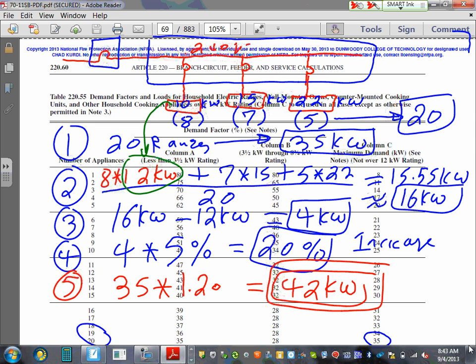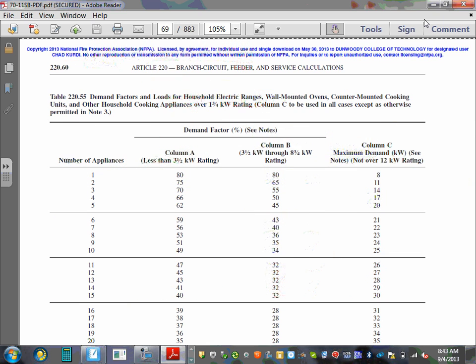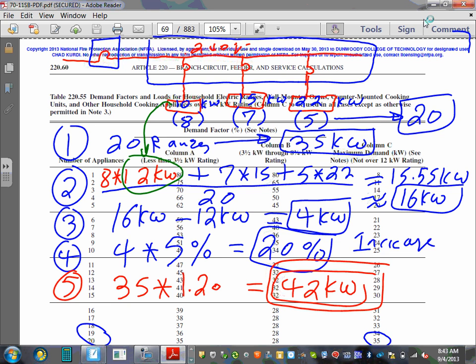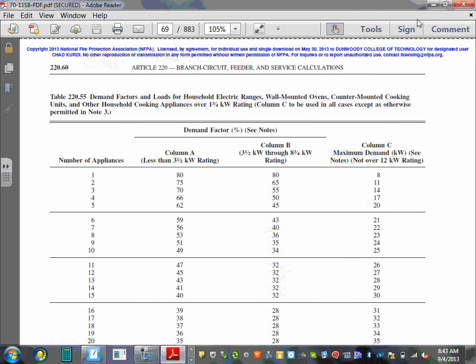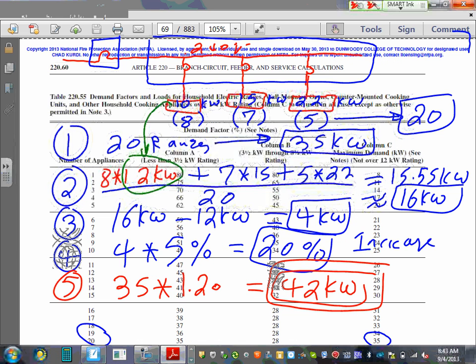Okay, so now that we did this, I'm going to take a snapshot of it. Now we know the kW. I'm going to erase that one and size based on the kW. Any questions, guys, about how to do the demand? We found the demand for the feeder, not the branch circuit. Can I emphasize the word feeder, not branch circuit? Okay, remember the 42, will you?